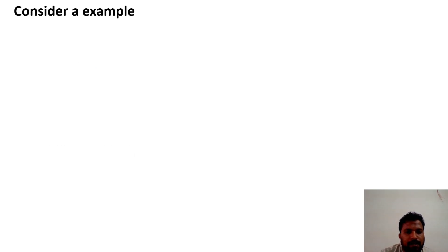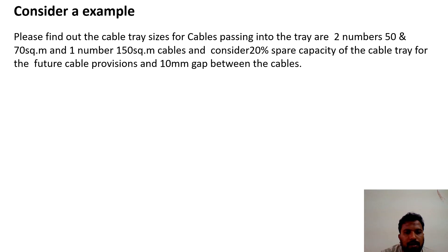Let's see an example. In this example, they give 2 number 50 square mm cables, 2 number 70 square mm cables, and 1 number 150 square mm cables, considering 20% spare capacity and 10mm gap between the cables. They will ask you to find out the cable tray size.